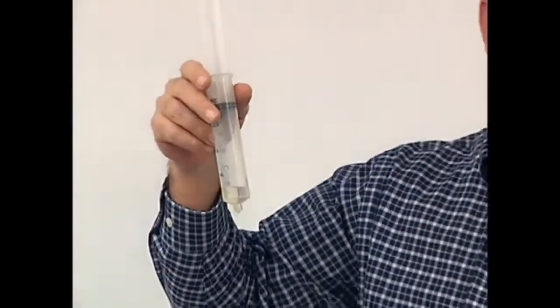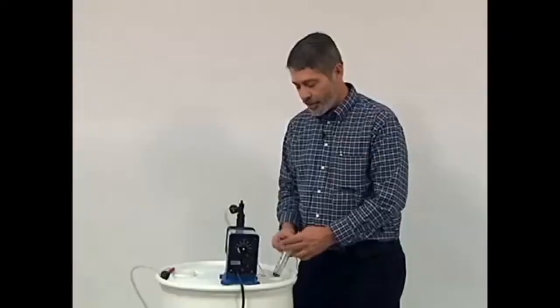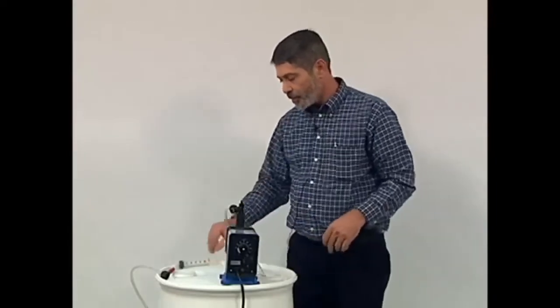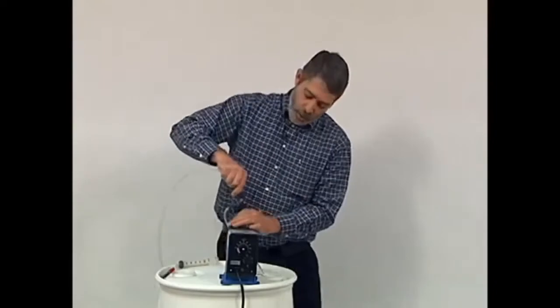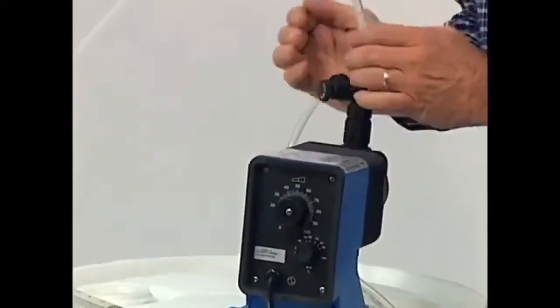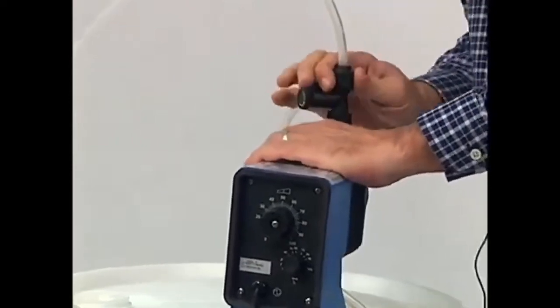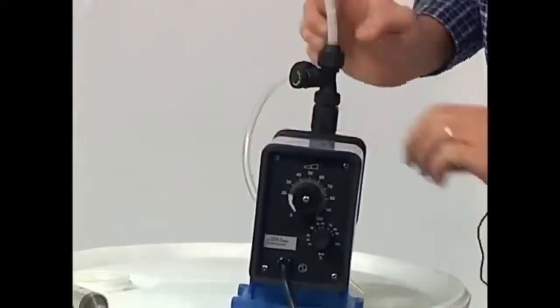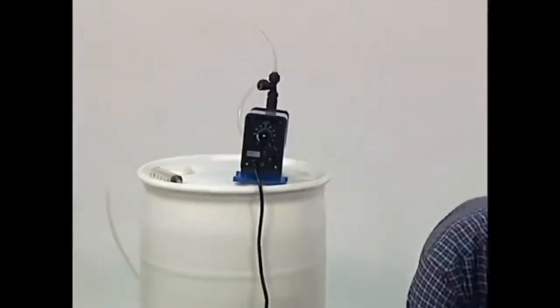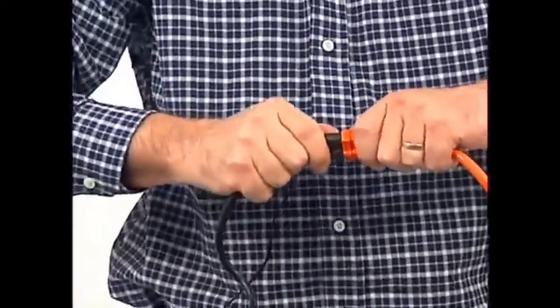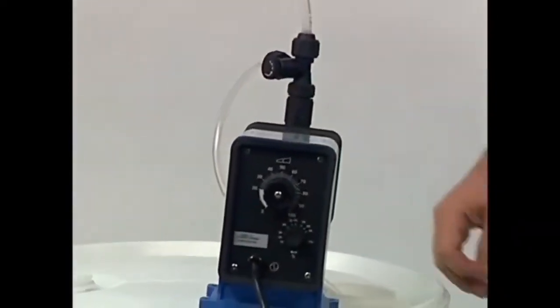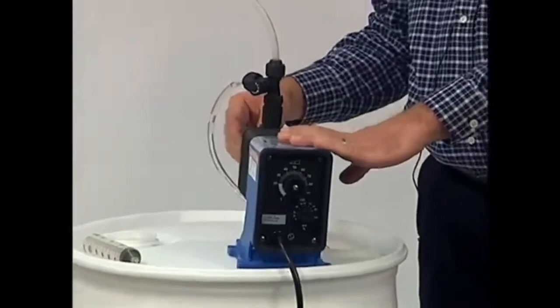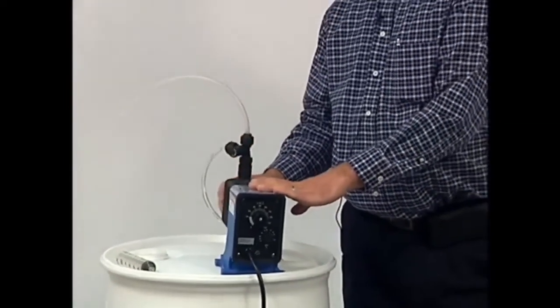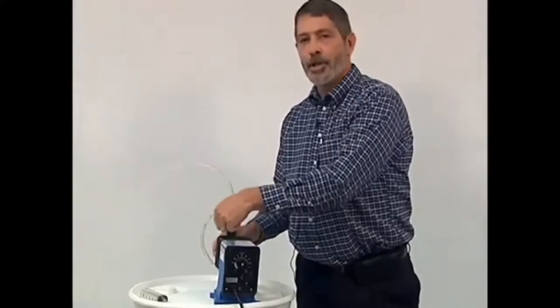As you can see, we've lifted water all the way through the pump so that the pump head and diaphragm are wet. The pump should be now ready to operate. Once you have gotten water back up to the pump head so that the pump is primed, simply reassemble everything and put the pump back in service. Again, your priming valve is a very nice tool, and once we have our liquid here, we simply close it and send the liquid to the system.